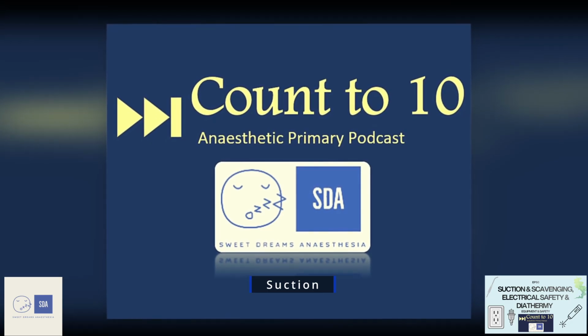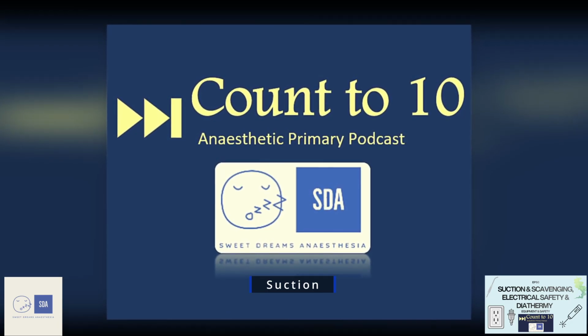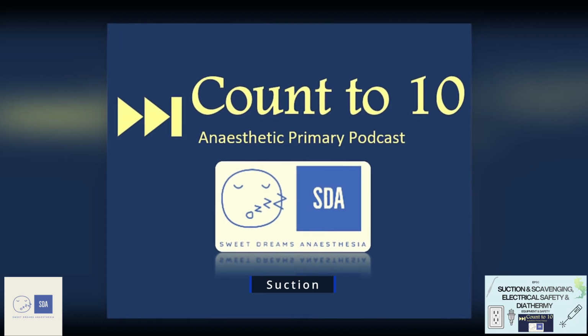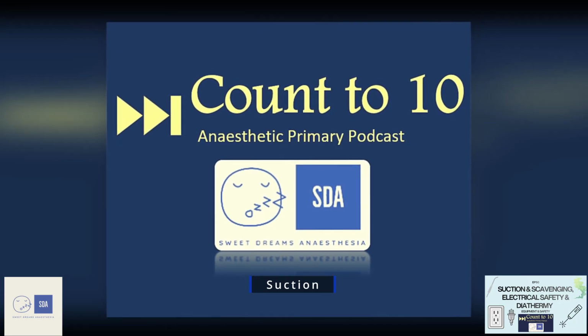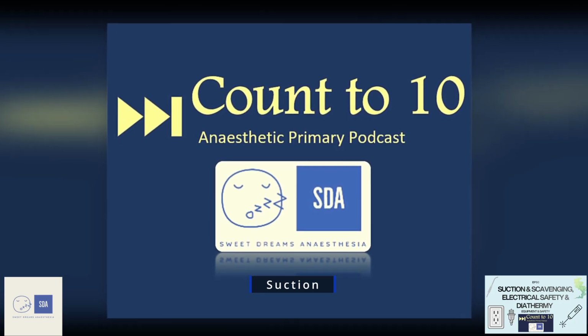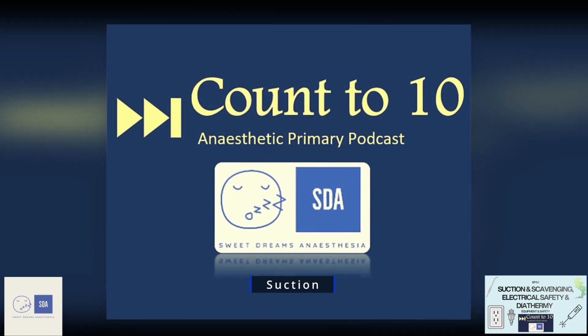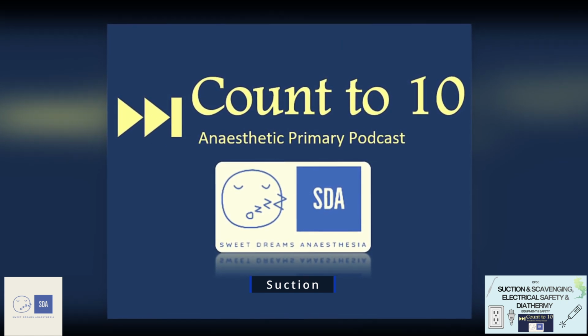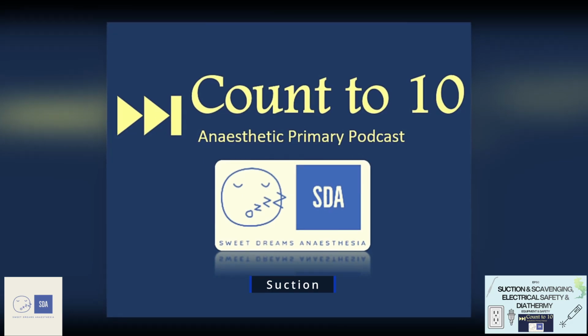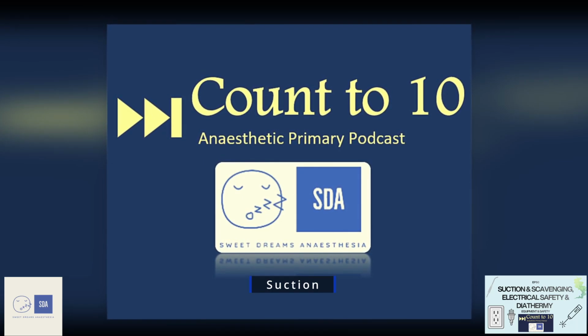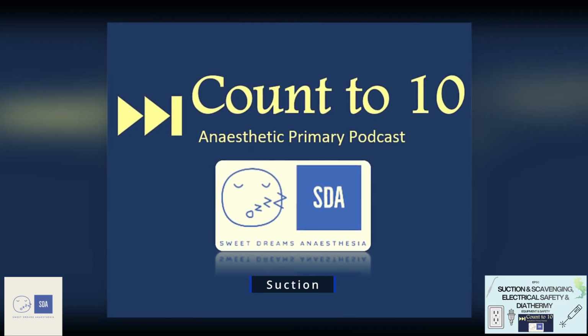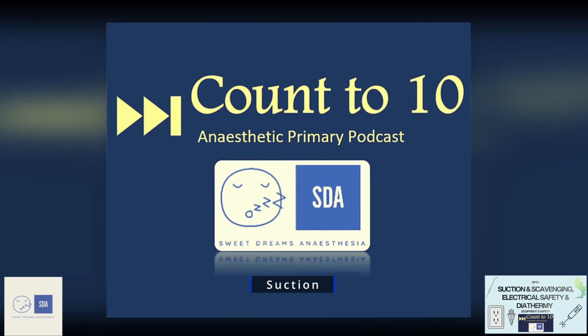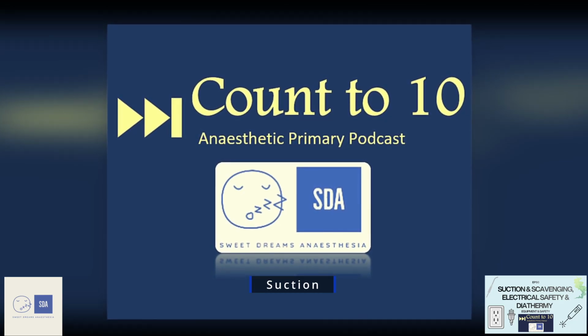Regardless of the type, each suction system has the same essential components that ensure it works safely. These components are a source of vacuum, a collection vessel or reservoir, and a delivery tubing. Within each of these three key components, you've got added components which increase safety. These are things like filters, which help prevent contamination, and pressure gauges, which allow us to know exactly how much pressure that suction device is generating, because as obvious as it sounds, too much pressure can damage tissues, and too little pressure is not enough to appropriately use the suction machine.